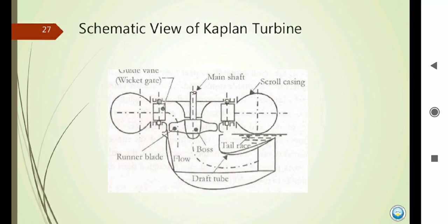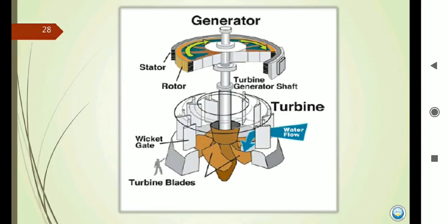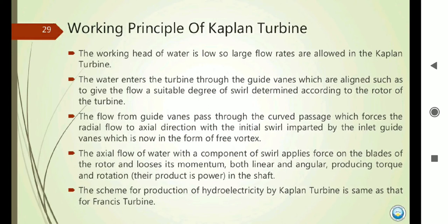In the Kaplan Turbine, the main shaft connects to the runner blades, with draft tubes always used. In the schematic diagram, you can see the axial flow turbine arrangement. Since the head of water is low, a large volume of water flows through the Kaplan Turbine. Water enters through the guide vanes, which give the flow a suitable swirl component determined according to the design of the turbine. The axial flow water with a swirl component applies force on the blades, and the water loses its momentum — both linear and angular — producing torque and rotation. The hydroelectric scheme using a Kaplan Turbine is similar to that of the Francis Turbine.